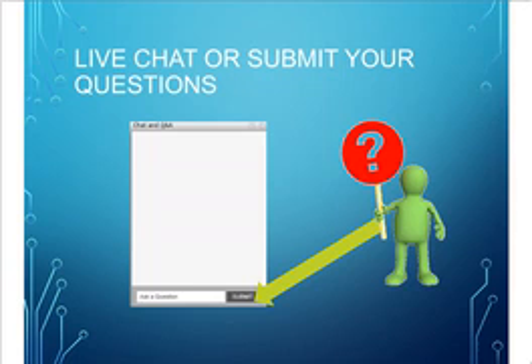Can you direct me on where it is required to have a genset outside? Yes, I believe that was a part of one of the NFPA requirements, and as I was looking at that, I think that it may not be a firm requirement. I see it listed as a requirement, but I bet you if I go back to the standard, it'll say we prefer to have it outside for access. But if I'm going to put my 90-minute UPS in a closet inside the building, why can't I use an internally mounted generator to do the same thing?